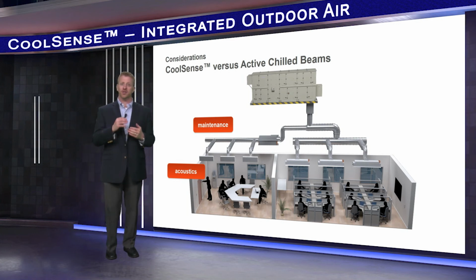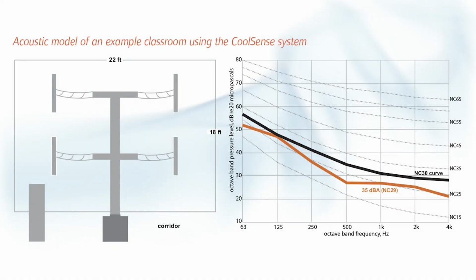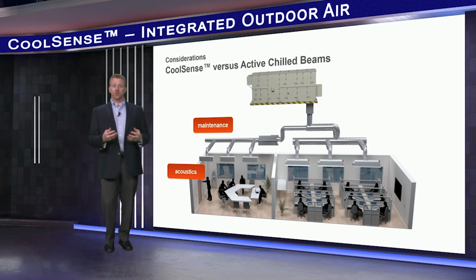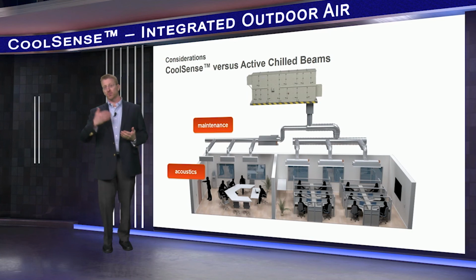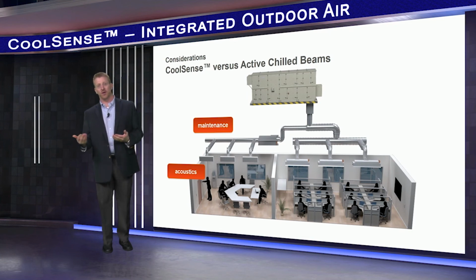If a sound issue is identified, actions can be taken. The CoolSense catalog contains example acoustic analysis for an office space and or classroom. For the example, we modeled the K-12 classroom down to 35 dBA. A practical element that has come up in discussions with customers is the placement of the CoolSense terminal unit. If sound and maintenance is a concern, you might simply locate it over the corridor and duct airflow into the space.